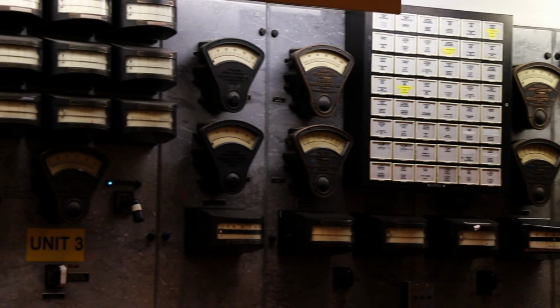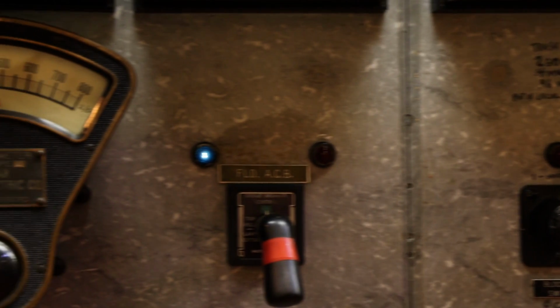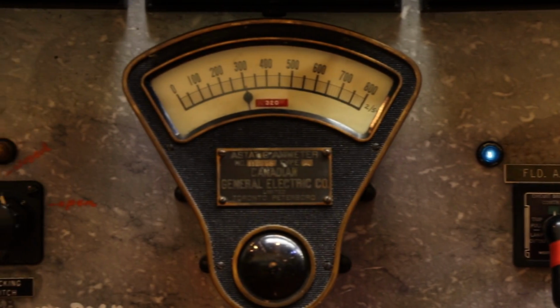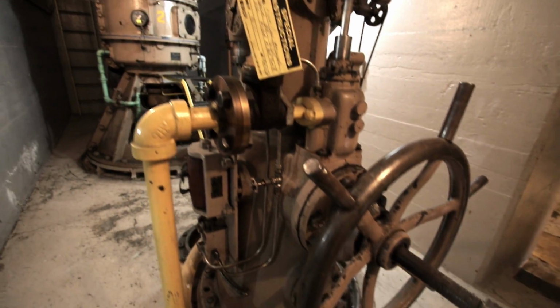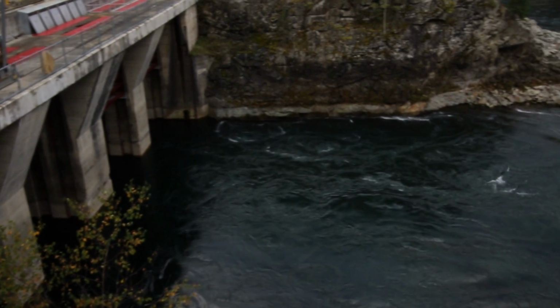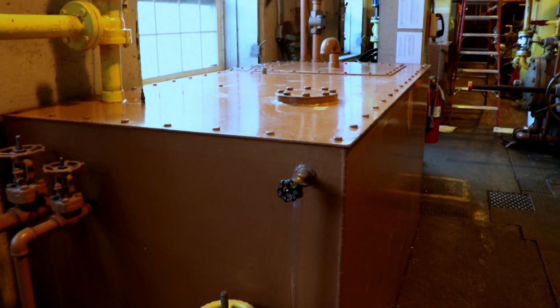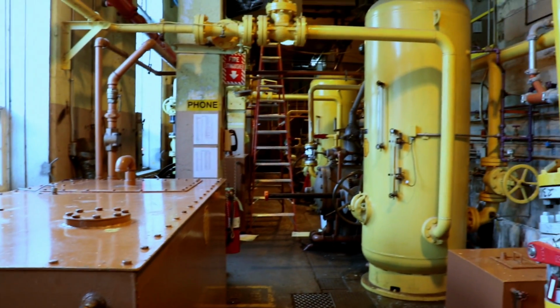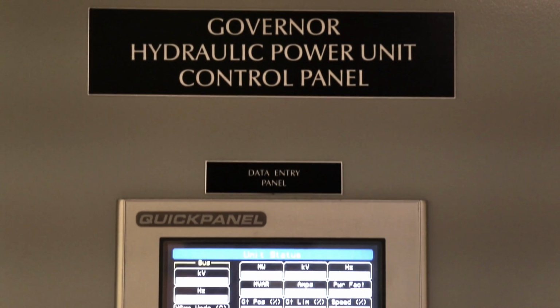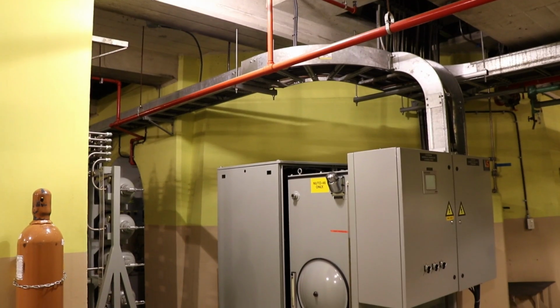The biggest areas of concern are reliability. Our equipment is old, it's obsolete, spare parts are hard to find, and it's hard to get technical assistance from the manufacturers if they don't exist anymore. The second area of concern is environmental. The older units use a high volume of oil in old tanks. Newer systems use much less oil and have modern spill containment.